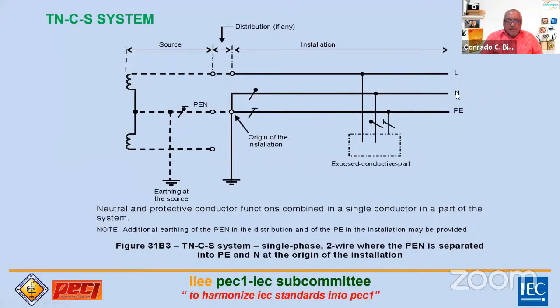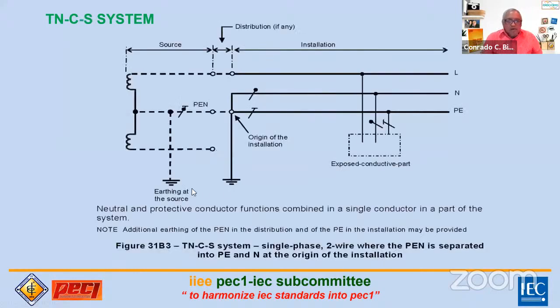Line neutral. Pero dito naman kasi, ginagamit natin yung phase-to-phase, yung nandun sa Line 1, so 240 yun, itong dalawa na to. Di naman tayo gumagamit ng 120 volts ngayon, wala tayong mga devices na mga equipment na ganyan. So mostly it's 240, so ang i-earth mo dyan, dun sa kabila. So this is the way how they connect it. TNCS ang tawag dyan for a single phase two-wire when the PEN is separated into PE and N at the origin of installation.